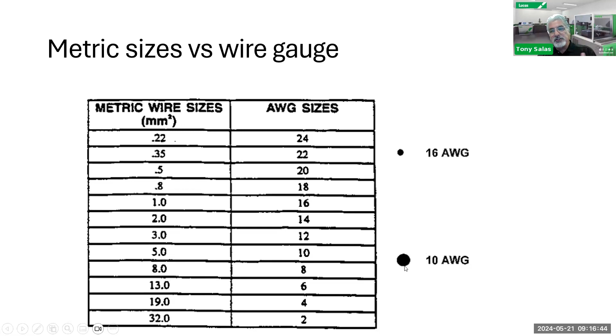Again, can the wire cause a high voltage drop? And the answer is yes. So your multimeter provides the ability to measure voltage, amperage, and resistance. Note that a multimeter can only measure up to 10 amps. So there are inductive ammeters to measure amperage, but those are for higher currents. Next time you look at your meter, if you haven't taken an electrical presentation with me, look at the bottom of that meter, and you're going to see that it has a maximum rating of usually 10 or 15 amps.